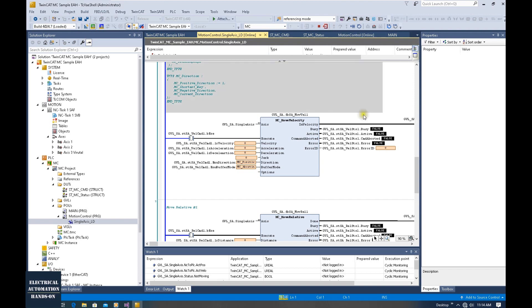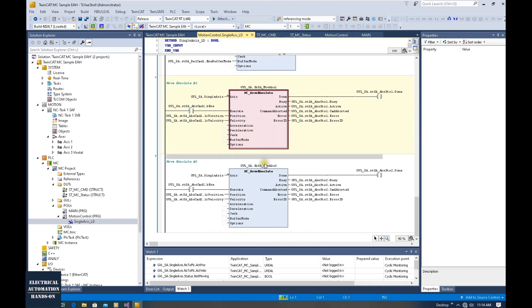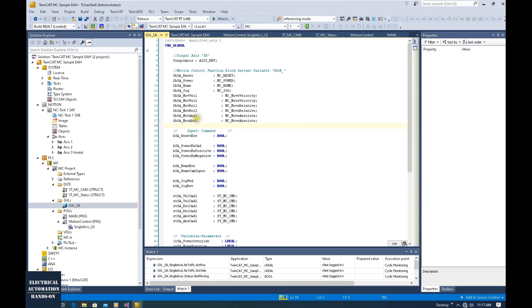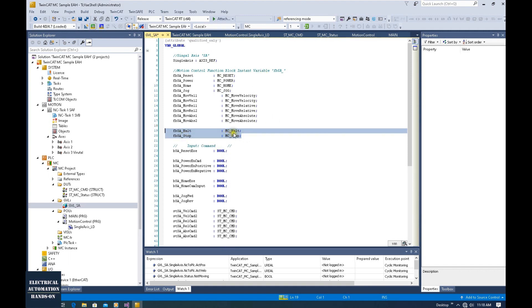Firstly, let's log out and shift to offline mode and program MC Halt and MC Stop. Let's first declare some variables — those variables include the trigger signal command, feedback status variables, and the instance variables. So let's go to the GVL_SA global variable list and first create the function block instance variable. For MC Halt, I create the tag FB_SA_Halt based on MC_Halt. And for stop, FB_SA_Stop based on MC_Stop. These are the instance variables.